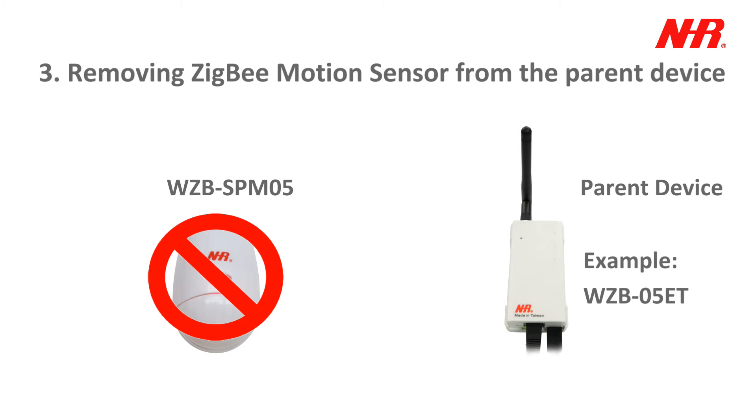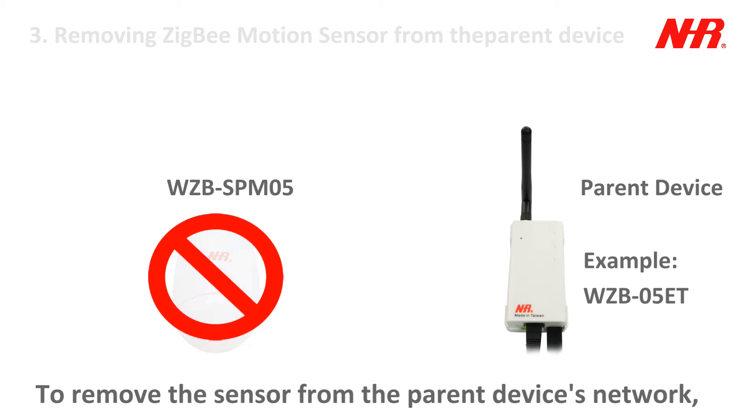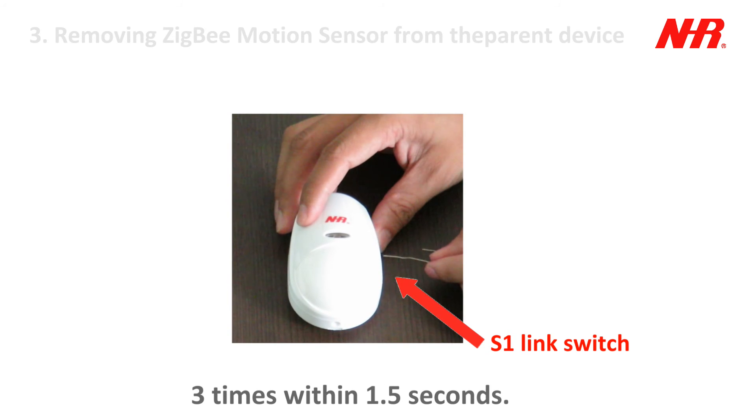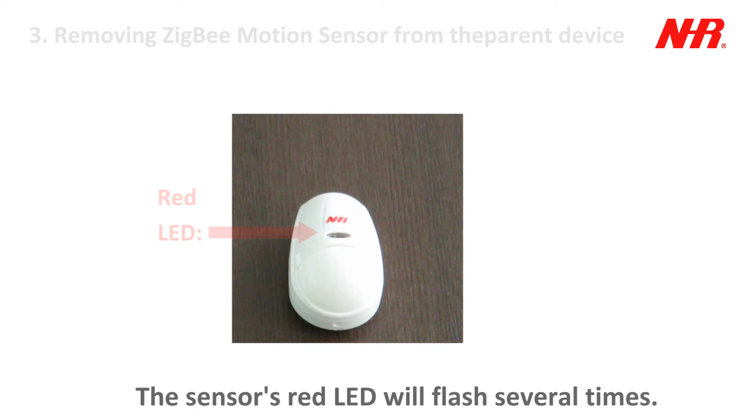Part 3: Removing the ZigBee motion sensor from the parent device. To remove the sensor from the parent device's network, press the sensor's S1 link switch 3 times within 1.5 seconds. The sensor's red LED will flash several times.